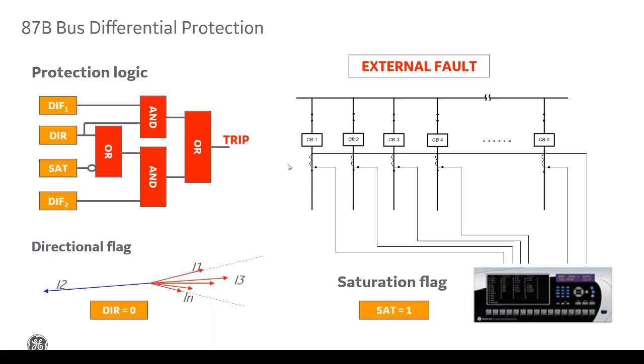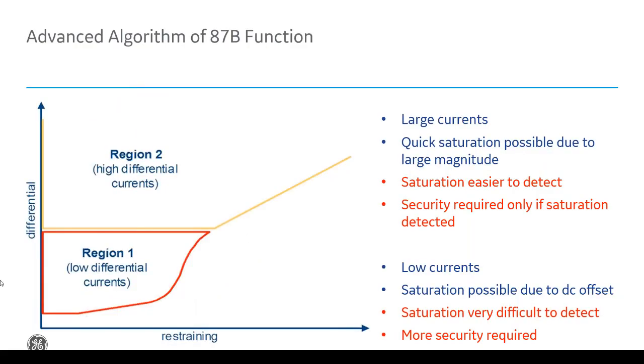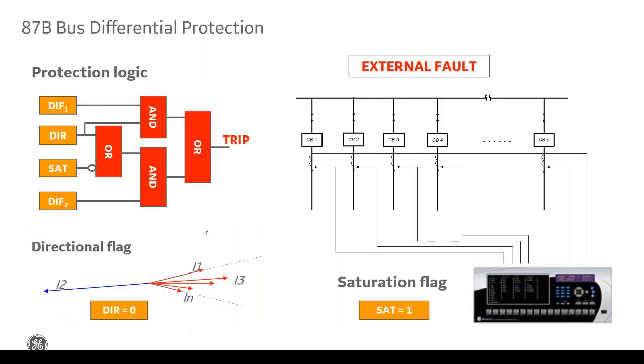Obviously, if the fault's on the bus, they should all be within plus or minus 90 degrees of each other. If there's an external fault, like I'm showing here, then at least one of them will be about 180 degrees out from the others. So during region 1, I basically always look at the directional flag because it's harder to detect CT saturation there, so I want more security. So the directional flag gives me security.